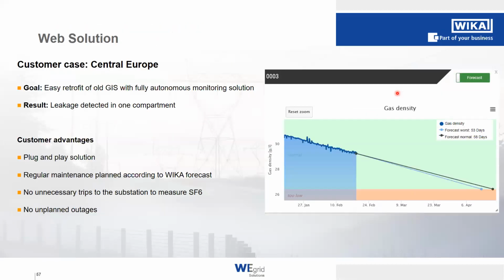I want to quickly show you a customer case for this solution, which we have recently done. We have done several, but this one is quite new and quite impressive. The goal of our customer was to easily retrofit an old GIS of over 30 years with a fully autonomous monitoring solution. And as a result, we were able to detect a leakage in one compartment, which you can see on the right side. And this leakage was quite severe, and we were able to predict when the threshold of low pressure will be reached.